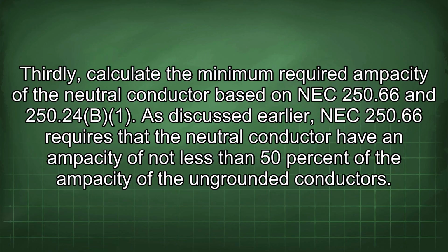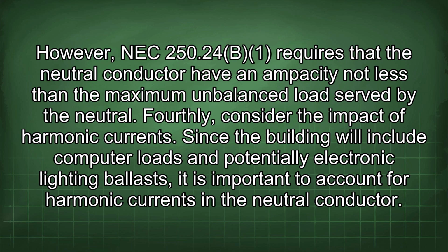Thirdly, calculate the minimum required ampacity of the neutral conductor based on NEC 250.66 and 250.24(B). As discussed earlier, NEC 250.66 requires that the neutral conductor have an ampacity of not less than 50% of the ampacity of the ungrounded conductors. However, NEC 250.24(B) requires that the neutral conductor have an ampacity not less than the maximum unbalanced load served by the neutral.